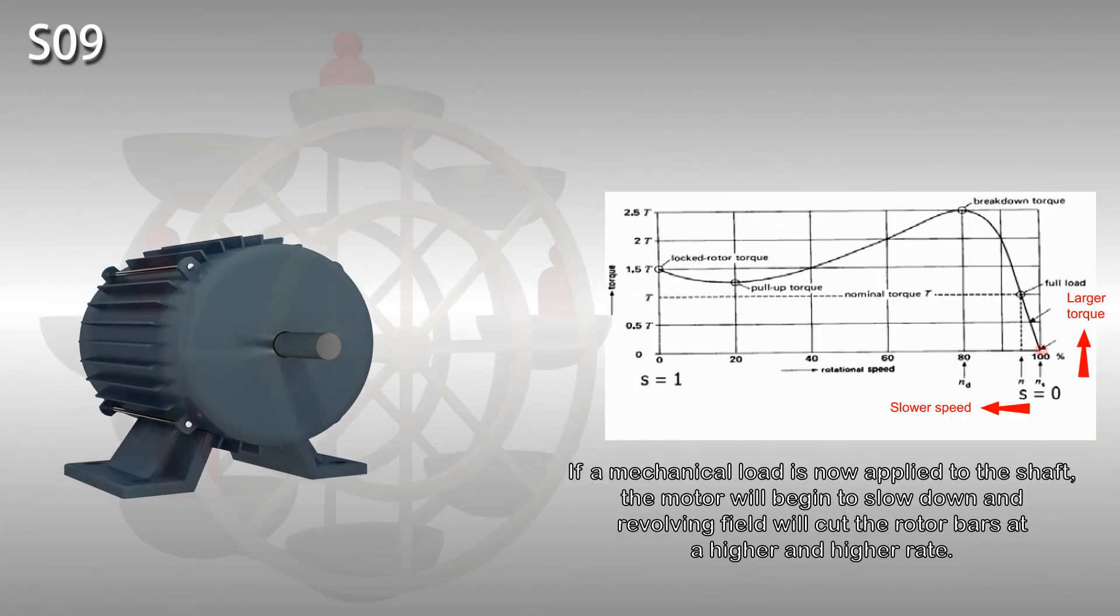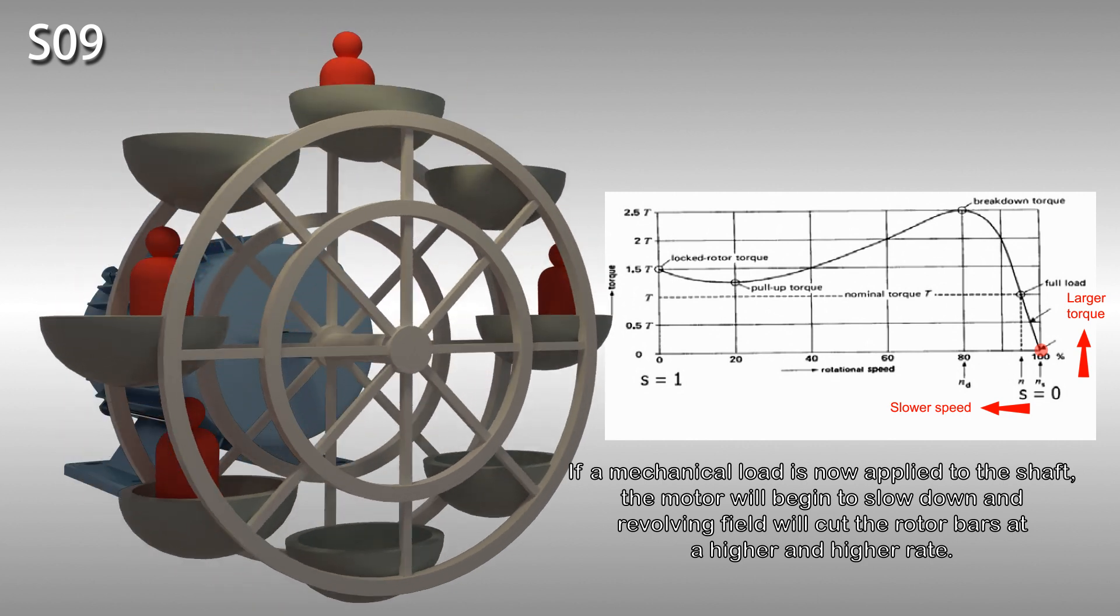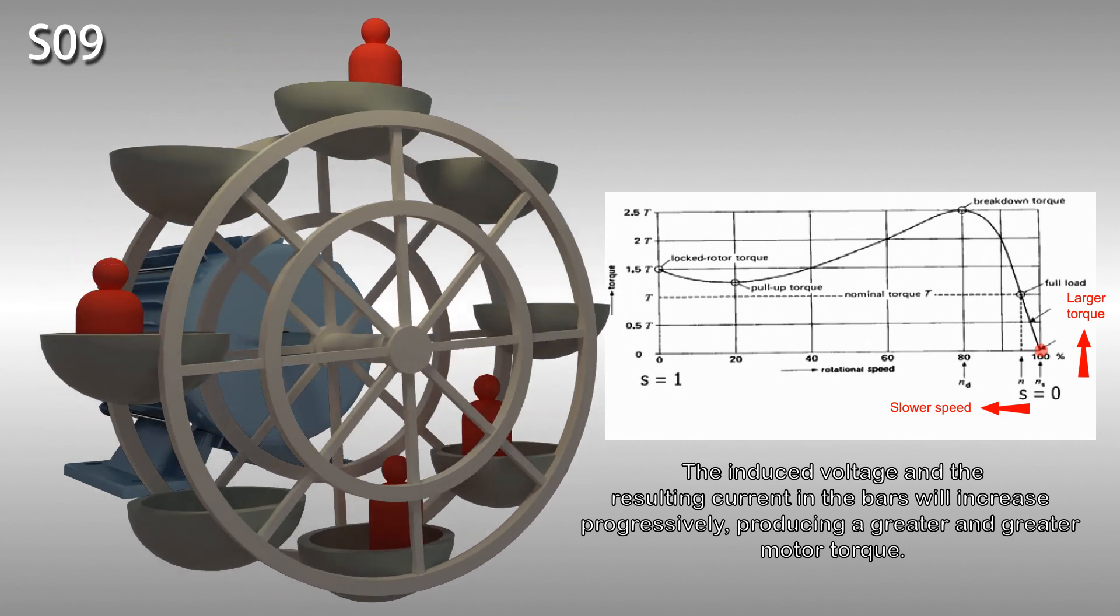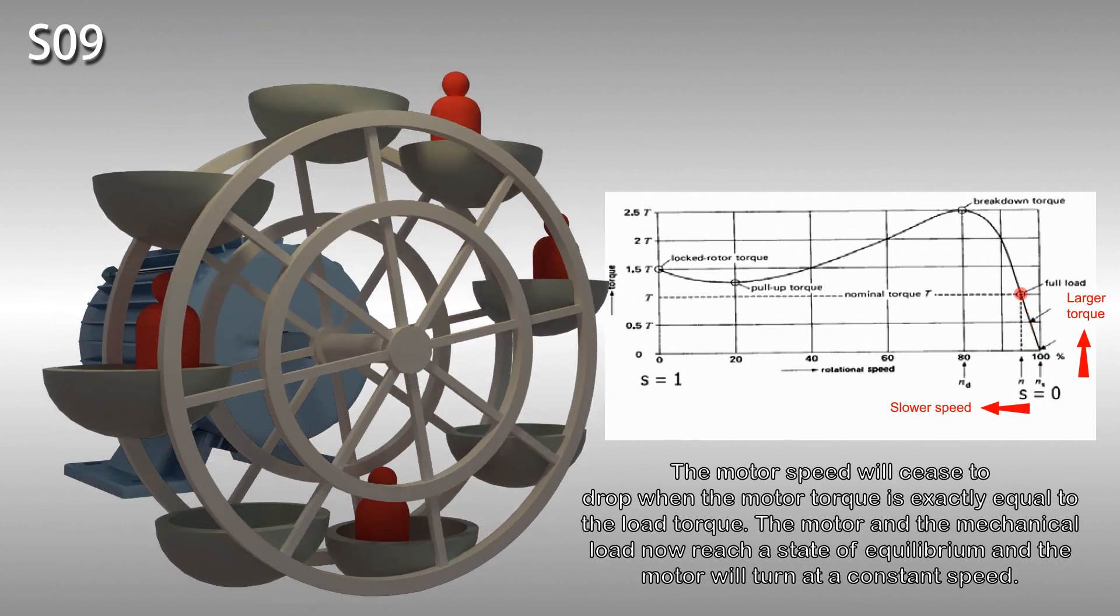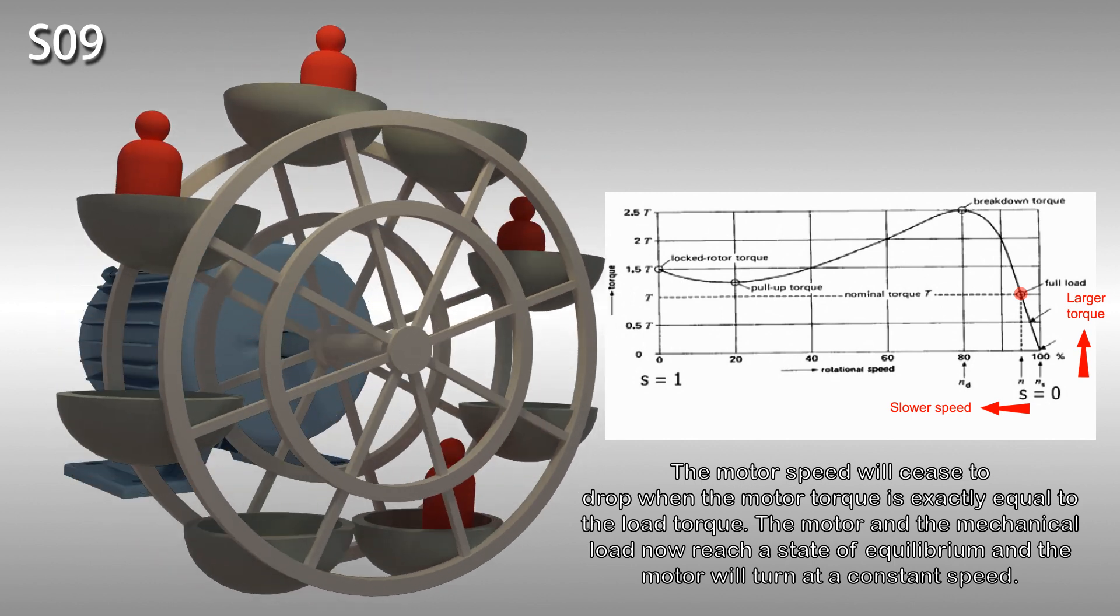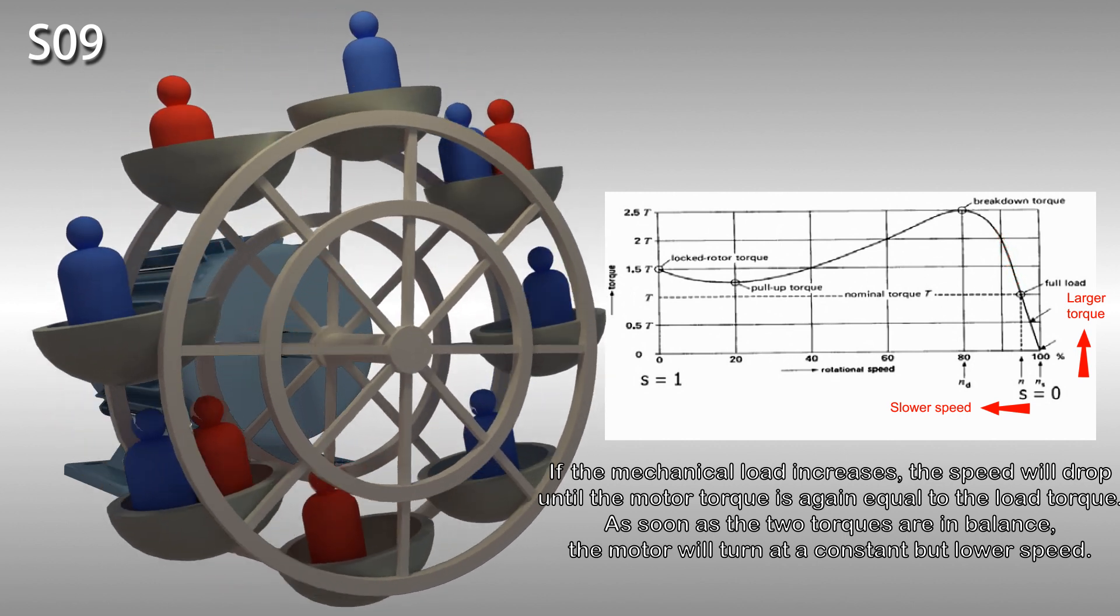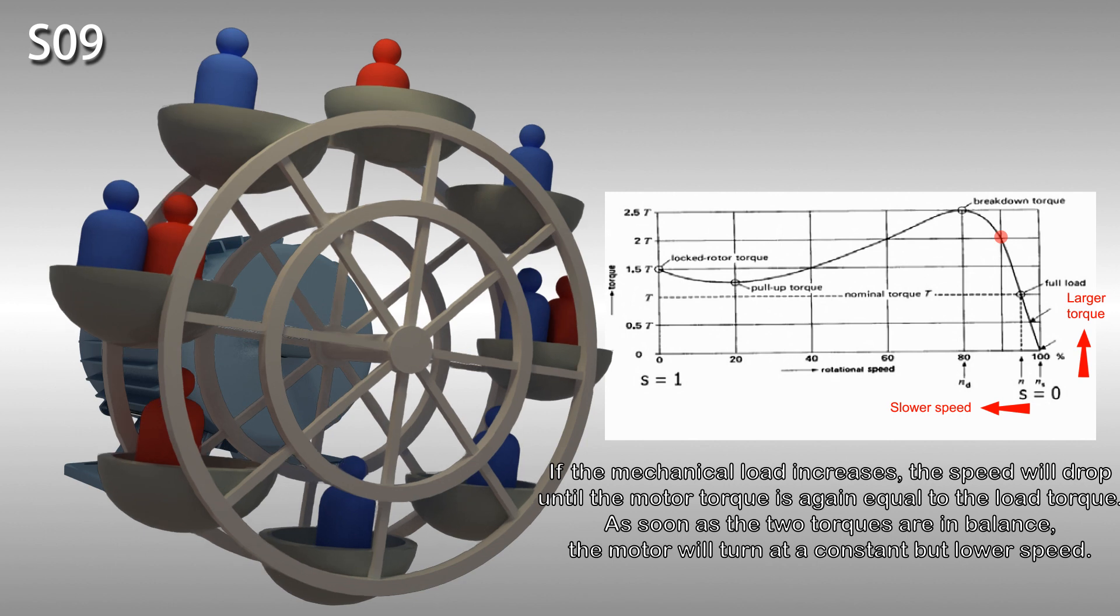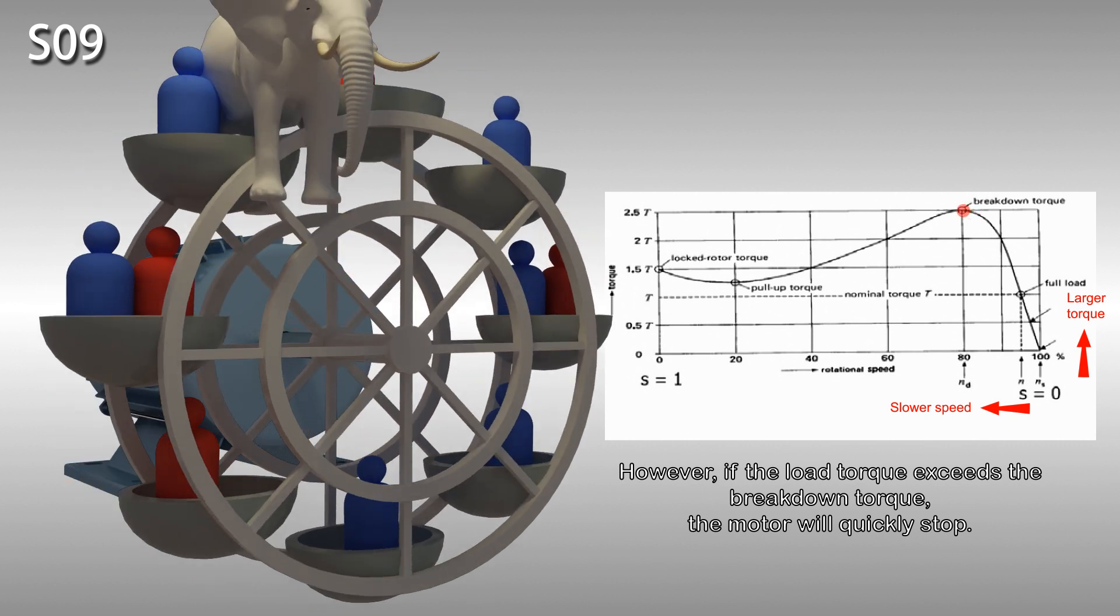If a mechanical load is now applied to the shaft, the motor will begin to slow down and the revolving field will cut the rotor bars at a higher and higher rate. The induced voltage and the resulting current in the rotor bars will increase progressively, producing a greater and greater motor torque. The motor speed will cease to drop when the motor torque is exactly equal to the load torque. The motor and the mechanical load now reach a state of equilibrium and the motor will turn at a constant speed. If the mechanical load increases, the speed will drop until the motor torque is again equal to the load torque. As soon as the two torques are in balance, the motor will turn at a constant but lower speed. However, if the load torque exceeds the breakdown torque, the motor will quickly stop.